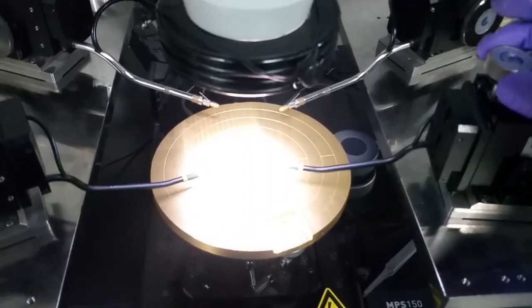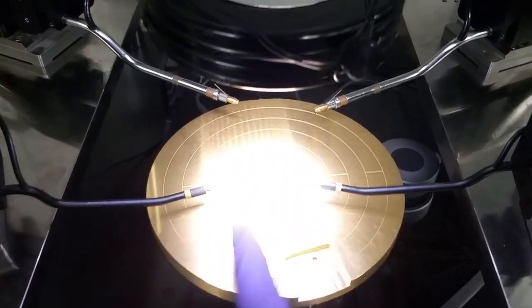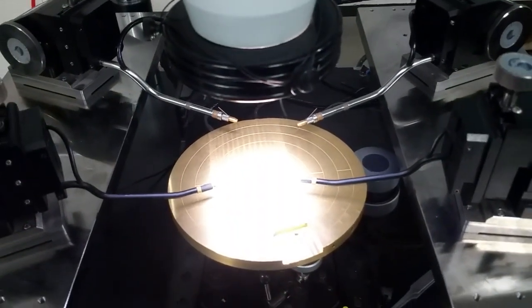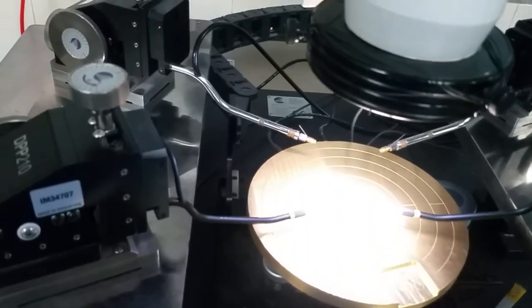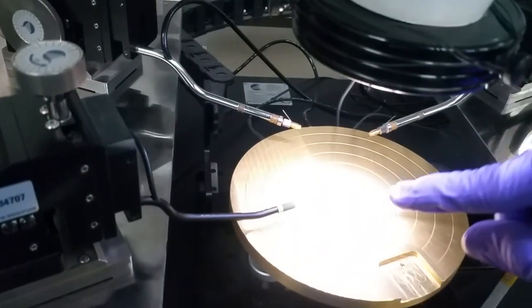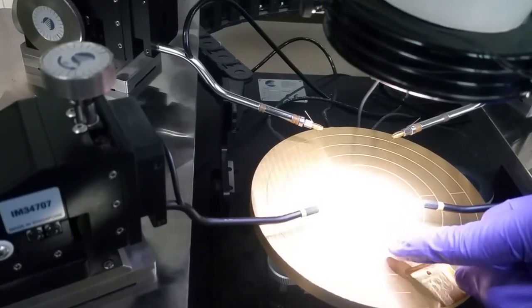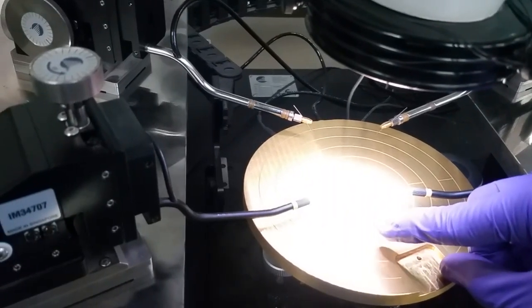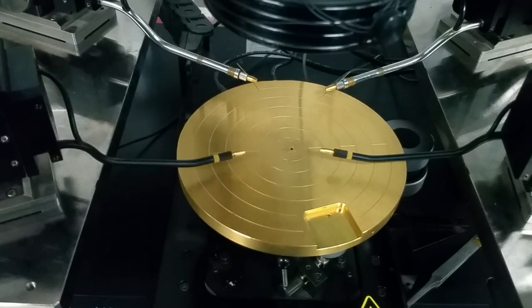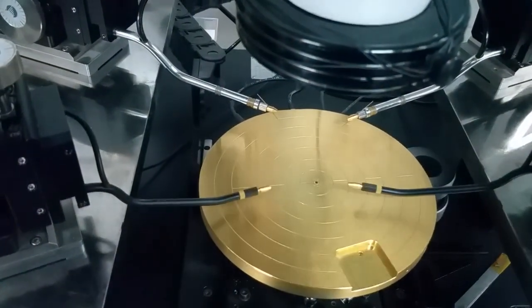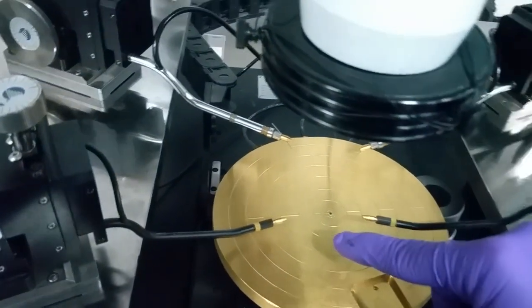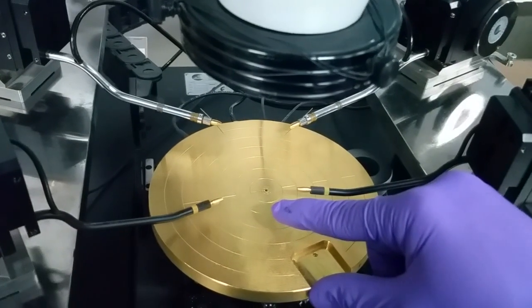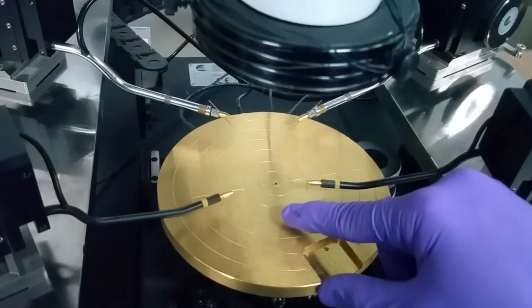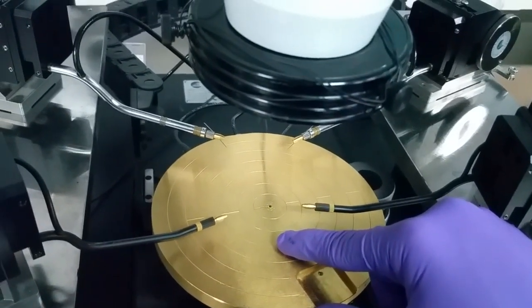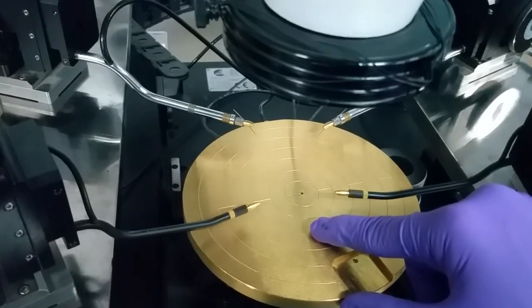And then you should use your micro manipulators to connect the probes, like this probe connected here to your sample, or whatever metal contact or pad you have made. When you are putting this probe down, the probe will go in Z from up to down. When it slightly touches your sample, the tip and the shadow meet, like here you can see. Now I am just demonstrating using my finger: this is my finger and below is the shadow. Similar is the case for a probe. When the probe is coming down, at one point the shadow and the probe will get connected. This is for silicon samples. For glass slides it may not be the case.